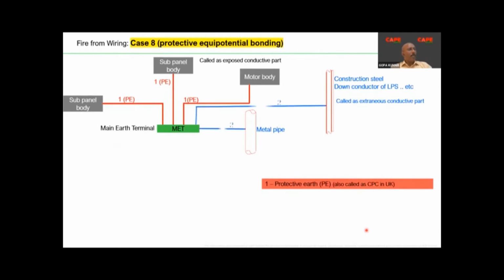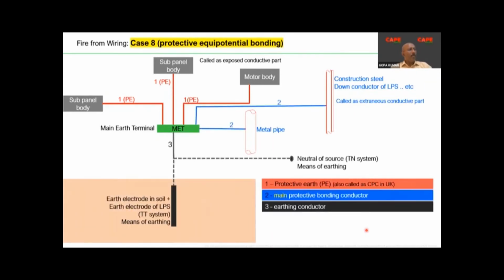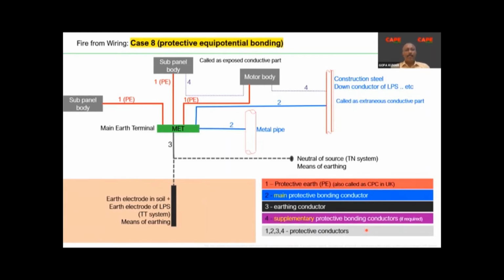Point number 8, protective equipotential bonding. It means every metallic item in your building, such as the metal water pipe, the metal gas pipe, the rebar in your building, and the exposed conductive parts, such as the panel board body and the motor body, must be interconnected in such a way that during a fault, there is no spark. For example, it can happen that there is a fault in one equipment in location A, but there can be a parallel spark in location B.